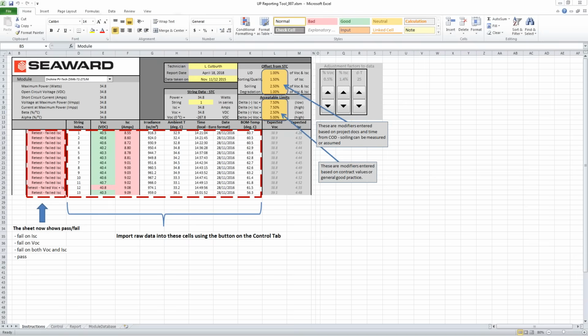I have a question here. Do you use the IEC standards to convert to STC? Yes, we do. We use the IEC standard. Does the test unit have a fuse for protection against overcurrent such as parallel strings? Sean asks. Sean, the rating of the unit is at 40 amps, and indeed it does have a fuse. The question is just how much of an overcurrent is put in the inside of the unit. If it's just above the 40, we should be okay. We should be able to contain that within the fuse. If the overcurrent is such that it's quite high, it can basically blow right through the fuse and damage the internal workings of the instrument.